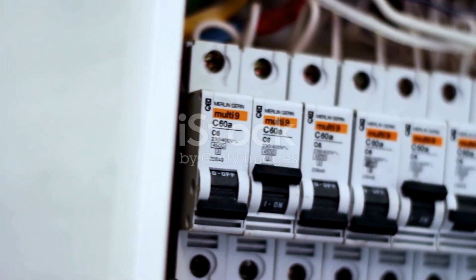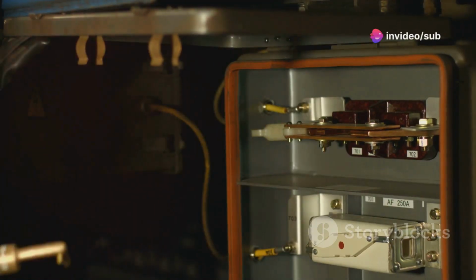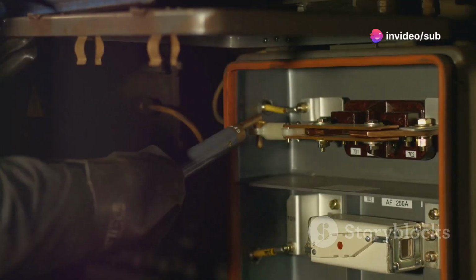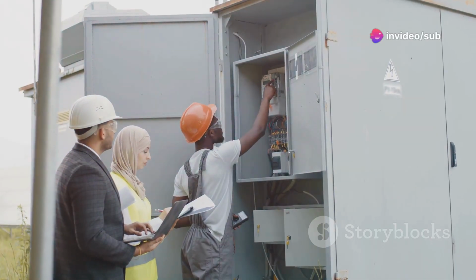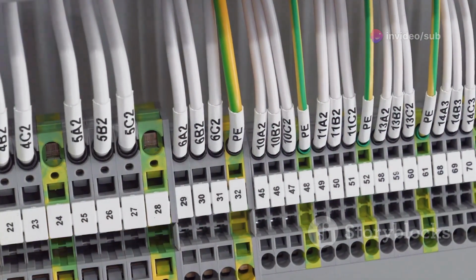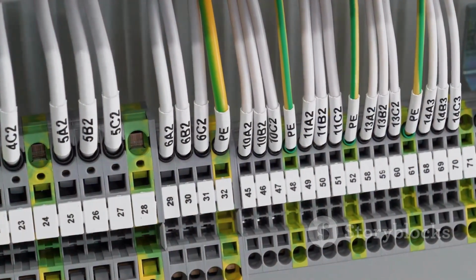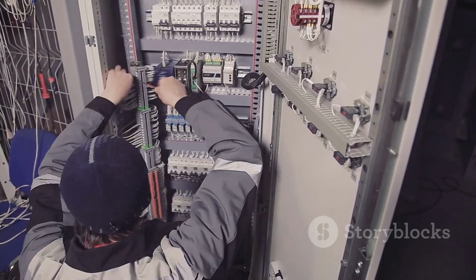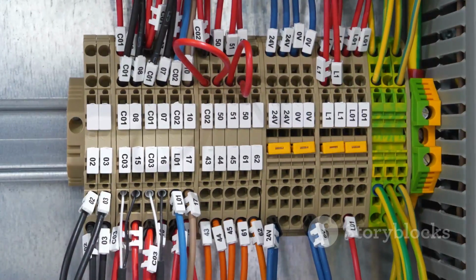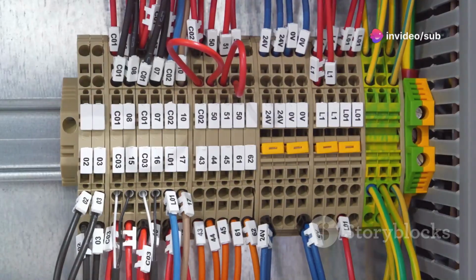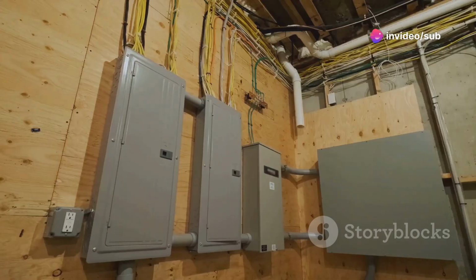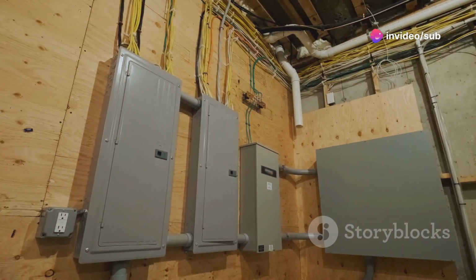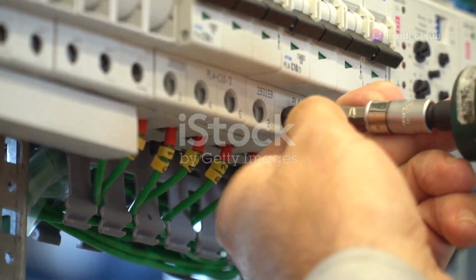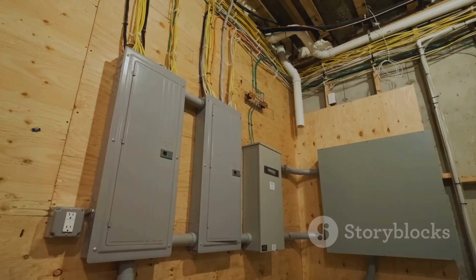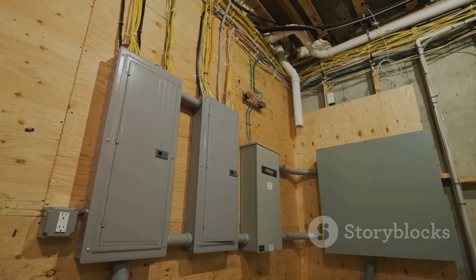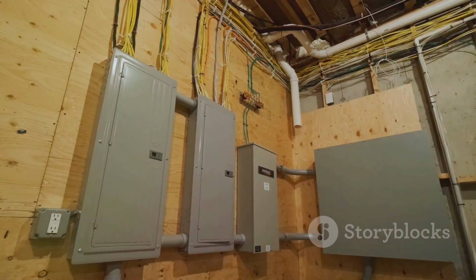Not a mistake. Seeing more than one terminal can definitely make you wonder if something went wrong, but don't worry, this is not a mistake. Manufacturers add multiple terminals on purpose. They design breakers this way for specific wiring needs and to increase flexibility in the panel. It's not about fixing a design flaw, it's about giving electricians and installers more options. This can be really helpful when circuits need to split or when the panel gets a bit crowded.